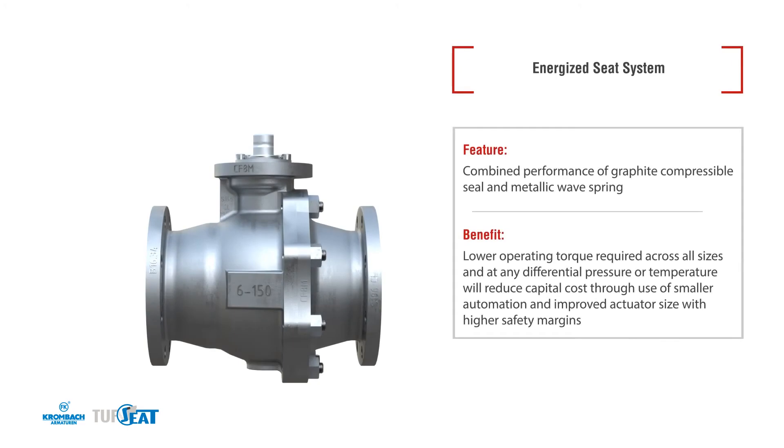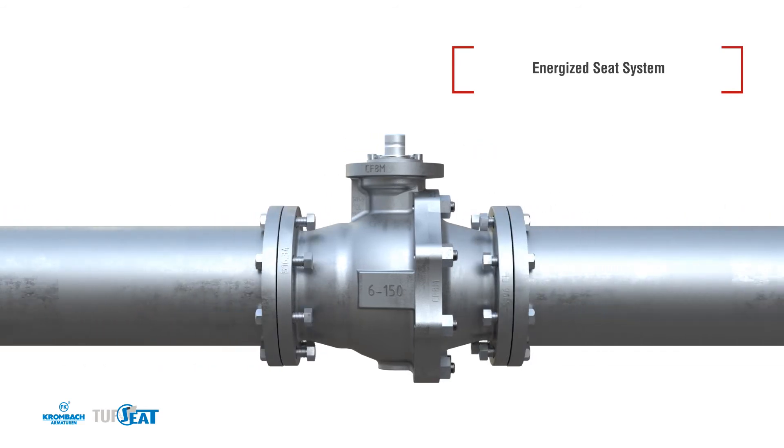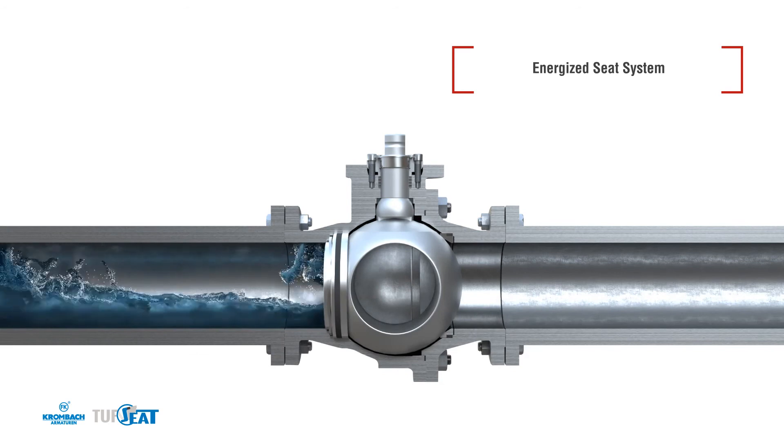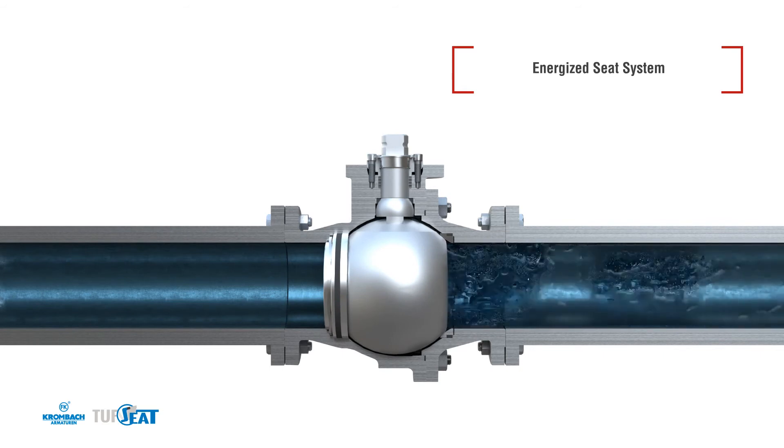The robust design of the seat of the new TufSEAT Performance Series Valves is the result of more than 40 years of experience in successfully serving the most difficult applications. By combining the compressible effect of the graphite seals with a metallic wave spring to handle larger deformations caused by temperature swings, the result is a low-torque valve with reliable seat leak performance. While the downstream seat is pressure-assisted and designed with simplicity in mind, the upstream seat is designed to ensure continuous operation in the toughest of applications.